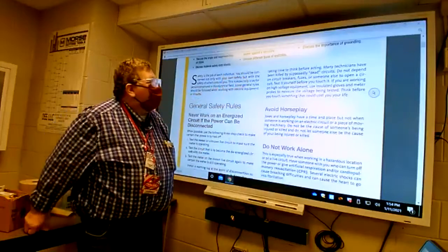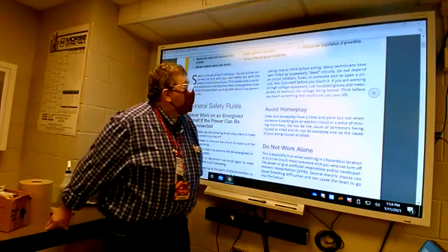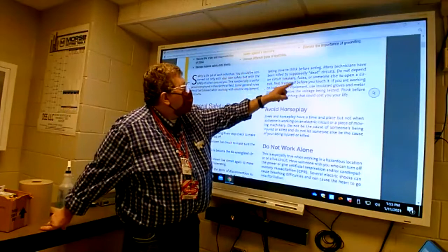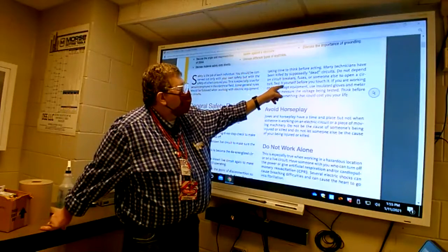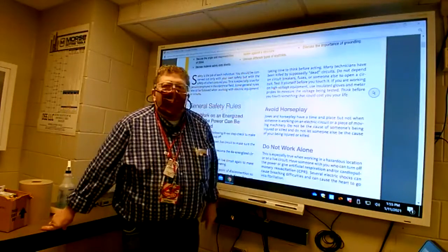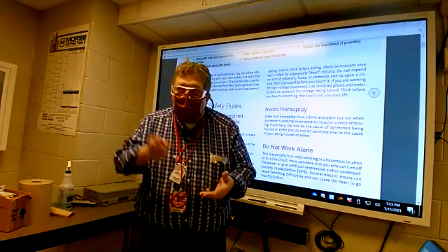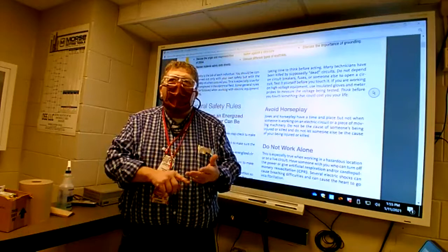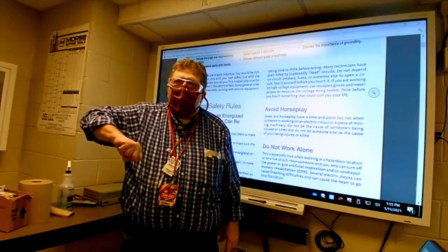Many people have been killed by supposedly dead circuits. It says don't depend on circuit breakers, fuses, or someone else to open a circuit. Test it for yourself before you touch it, which means do the three-step check with your meter yourself. Don't go by somebody else's word. Don't go by the fact that switch is down and locked out.